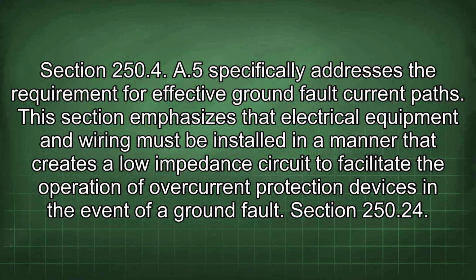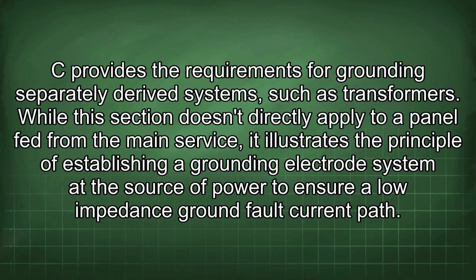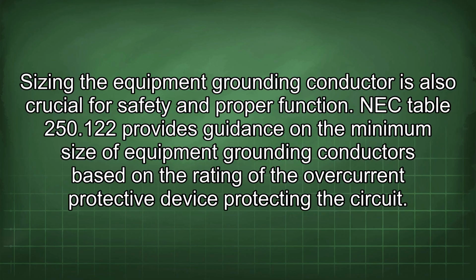Section 250.24(C) provides the requirements for grounding separately derived systems, such as transformers. While this section doesn't directly apply to a panel fed from the main service, it illustrates the principle of establishing a grounding electrode system at the source of power to ensure a low impedance ground fault current path. Sizing the equipment grounding conductor is also crucial for safety and proper function.